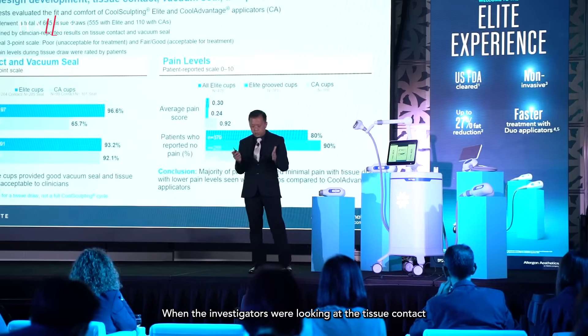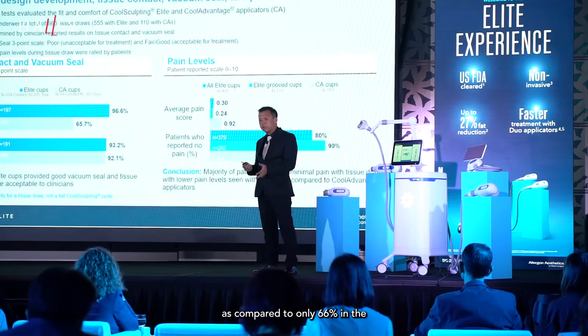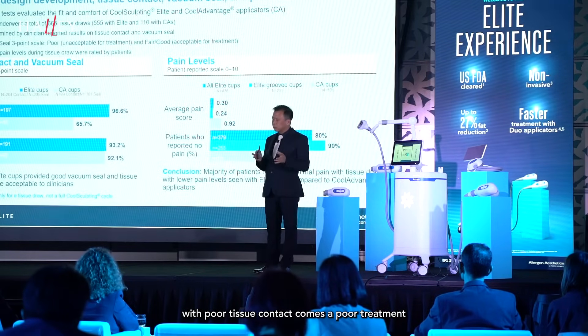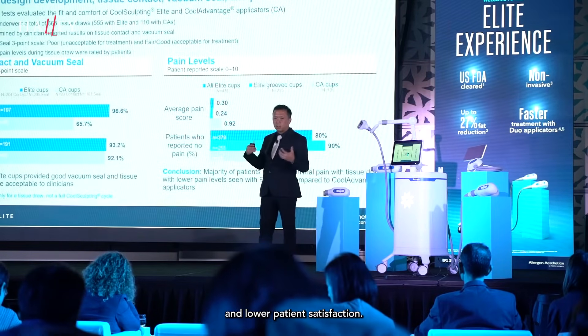When the investigators were looking at tissue contact, they found that the Elite applicators were much better than the CoolAdvantage applicators, in that 96% or 97% of treatments — or rather tissue draw — had acceptable or good tissue contact, as compared to only about 66% in the CoolAdvantage range of applicators. This is really important because with poor tissue contact comes a poor treatment, and with a poor treatment, there would probably be a higher chance of pop-offs and other problems, and lower patient satisfaction.